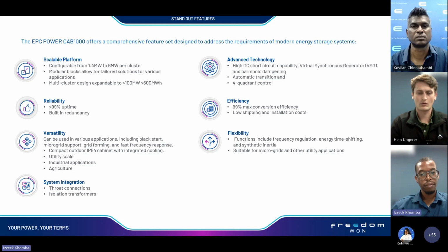Another important feature is the 4-quadrant operation, which means it has an extended reactive power capability to inject up to the rated capacity of reactive power into your load, which can also be used for power factor correction. It's a very efficient inverter with up to 99% conversion efficiency, depending on load conditions. It's also a flexible solution that can be used for microgrids, off-grid solutions, grid-connected systems, and utility applications. It can be used for voltage regulation on grid lines as well.